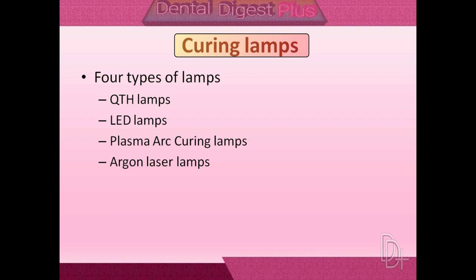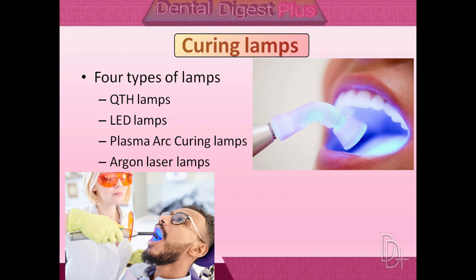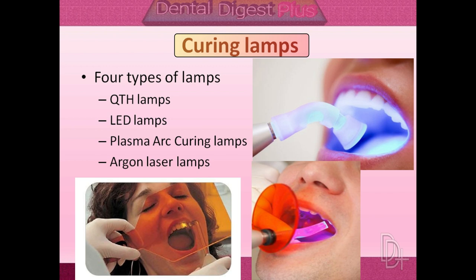Regarding precautions when using curing lamps: the light emitted by curing units can cause retinal damage if a person looks directly at the beam for an extended period of time, or even for short periods in the case of lasers. To avoid such damage, never look directly into the light tip, and minimize observation of reflected light for longer periods. Protective eyeglasses and various types of shields that filter the light are available for increased protection for both clinical personnel and patients.